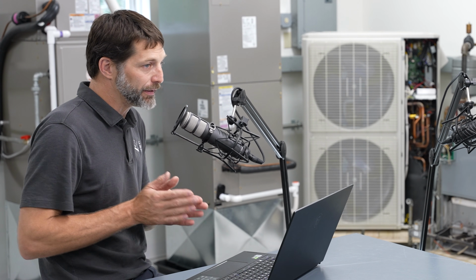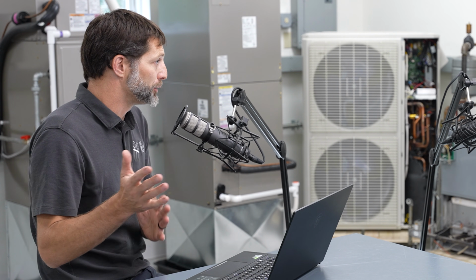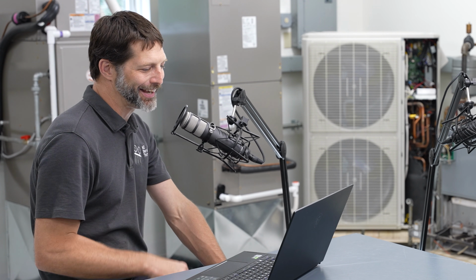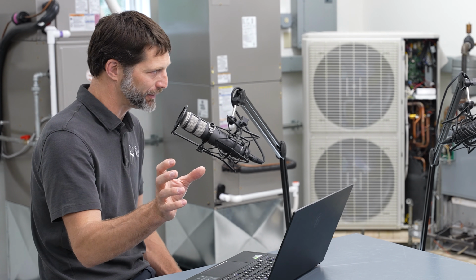Yeah. So say it's a multi-zone unit and it does not have any branch box. If it has a branch box, the EEVs are all going to be there. If it's a multi-zone system without a branch box and the line set goes from the outdoor unit to each of the individual indoor units, you're going to have an EEV per zone in the outdoor unit. But like you said, you could have an EEV controlling maybe 2 indoor units in the future. We don't know, so you're really going to have to pay attention to all that stuff, because those indoor units don't have an EEV on them.